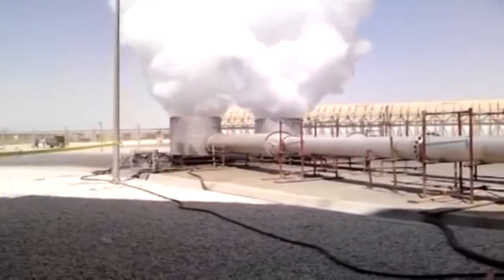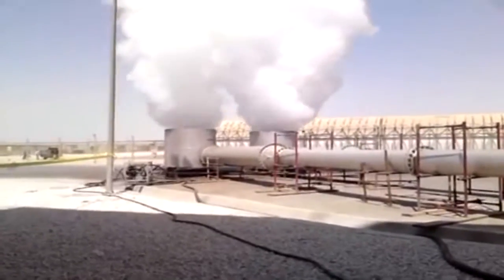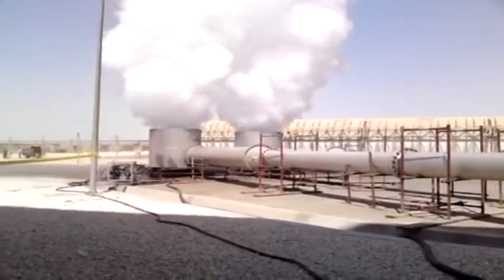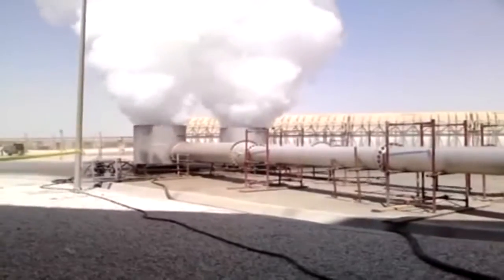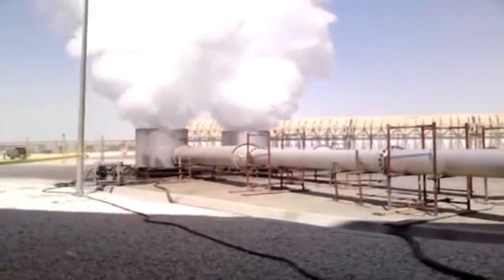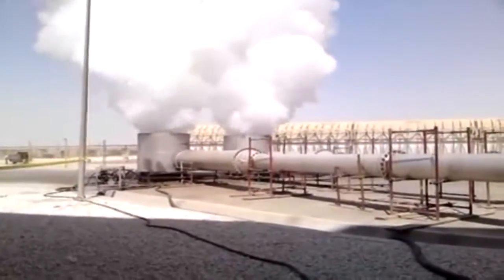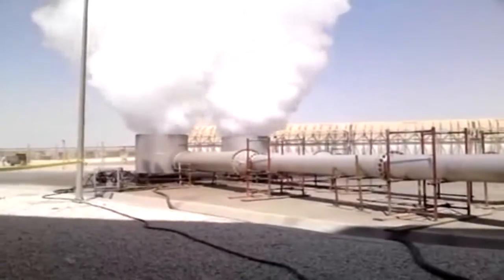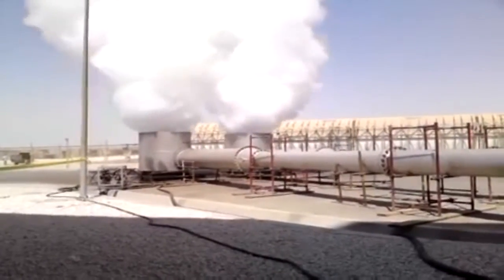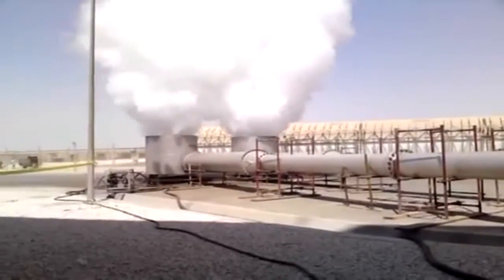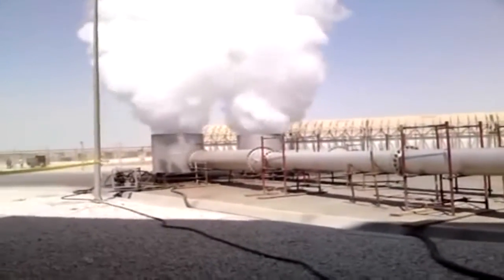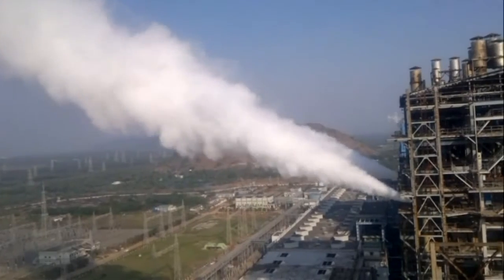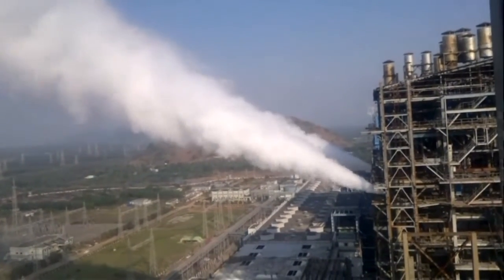The advantages of steam blowing are principally its effectiveness. It is good at removing mill scale and debris. However, there are disadvantages, and these are also, ironically, its effectiveness, with cost, disruption, risk of damage and safety. The effectiveness is subjective. We use targets to check for pockmarks. The cost of steam blowing can be high. It is a lengthy process, and the cost of engaging a specialist contractor is also high. Therefore, allow for this in the budget.